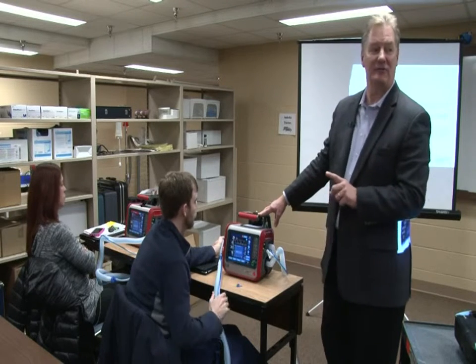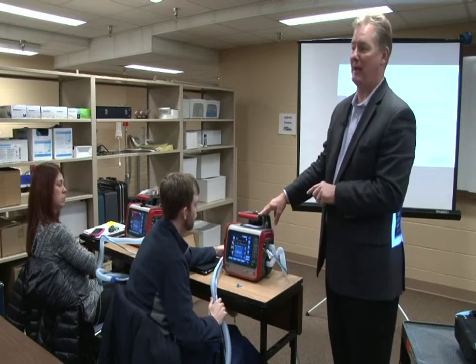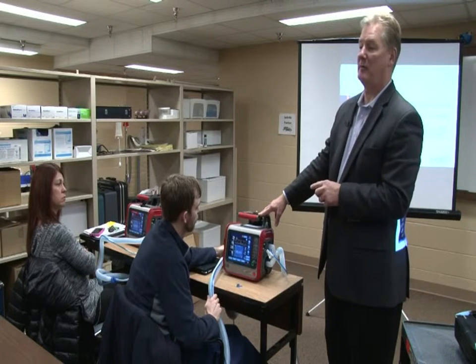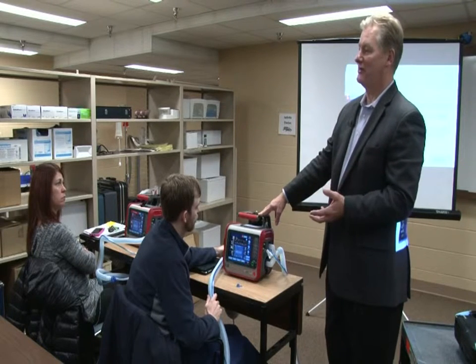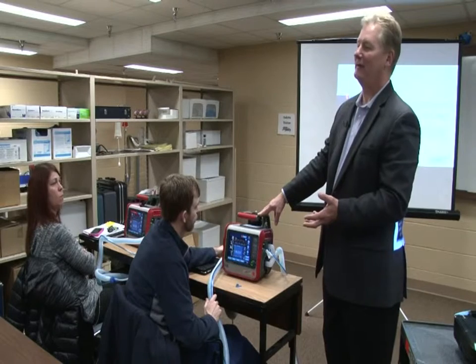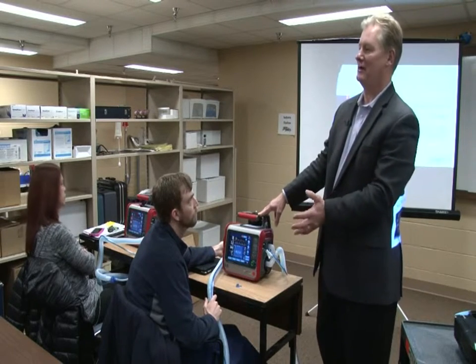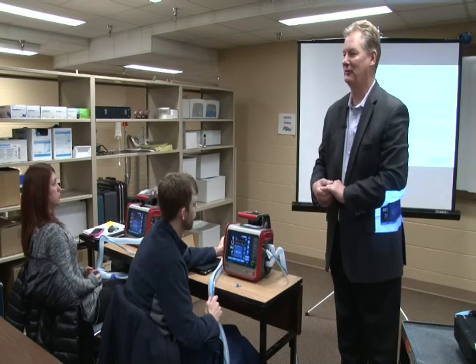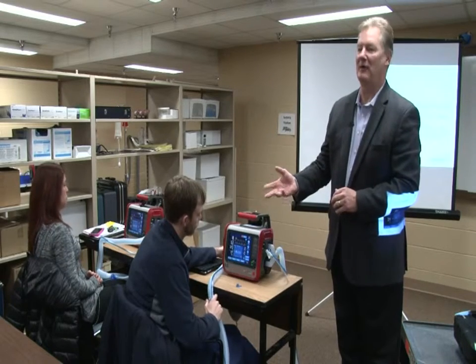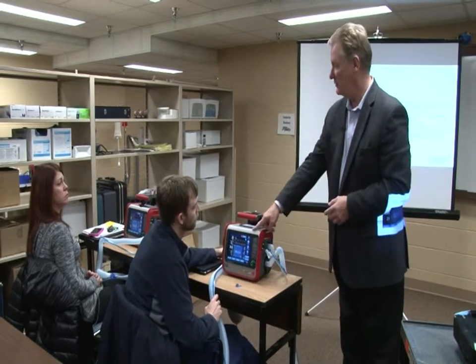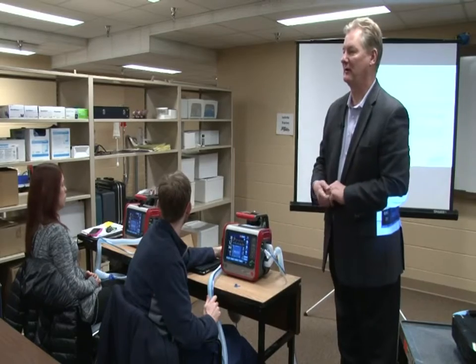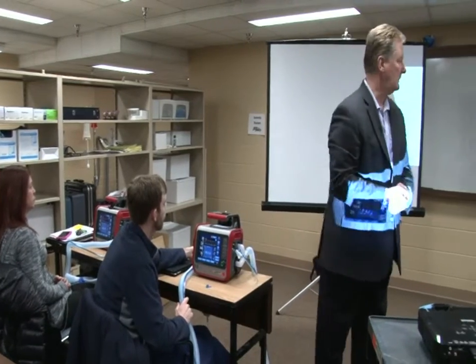And the primary reason for that is that some of the measured parameters, specifically minute volume and rate, are based on an average of 8 breaths. So when you turned it on, there was nothing for it to average, and so it waits for a few breaths before it can present numbers. And if you didn't do that, when you turned it on, it would start alarming right away, which it was, but the alarms have since corrected themselves and gone away. Okay?